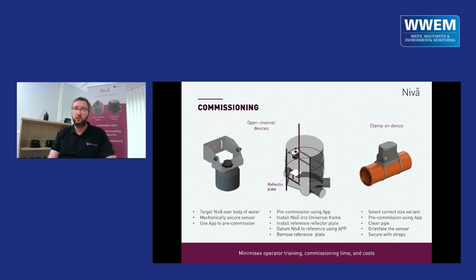The clamp-on is super easy to do because the pipe size input gives you both reference levels, full and empty, so you get that set up before you get out of your car. Any output options, alarms, all those kinds of things can be done. When you get to the pipe, clean off the mud - it doesn't need to be shiny clean, but a thick layer of gravelly mud is best removed. Get the meter flat and level, then strap it to the pipe, connect power and data, and you're away. Any post-commissioning validation can be done from Bluetooth range, and that should be it.